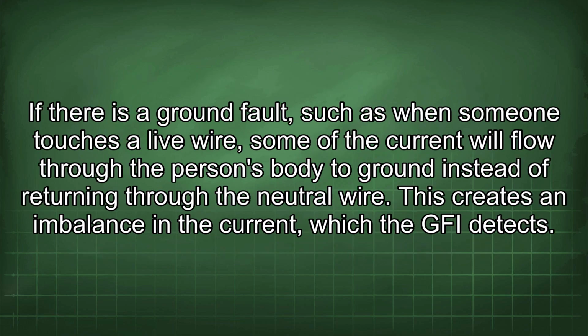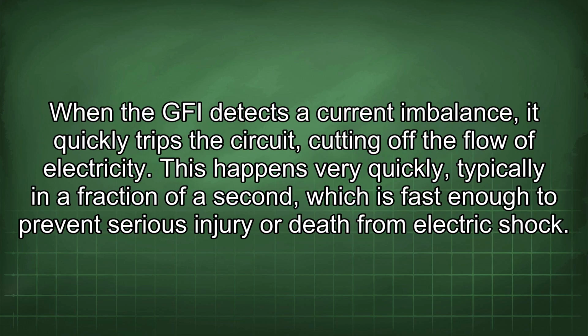If there is a ground fault, such as when someone touches a live wire, some of the current will flow through the person's body to ground instead of returning through the neutral wire. This creates an imbalance in the current, which the GFI detects. When the GFI detects a current imbalance, it quickly trips the circuit, cutting off the flow of electricity.